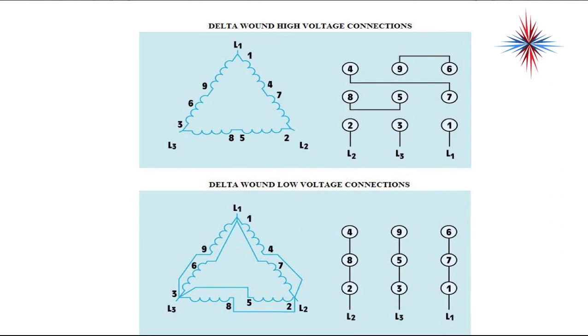So, three-phase motors, again, no start components, no capacitors. They will run backwards if connected incorrectly. Just reverse two leads and you'll be fine. It will turn it around. And if you have to troubleshoot it, one of the first things you want to do is ohm out all the windings and make sure the windings are the same resistance.